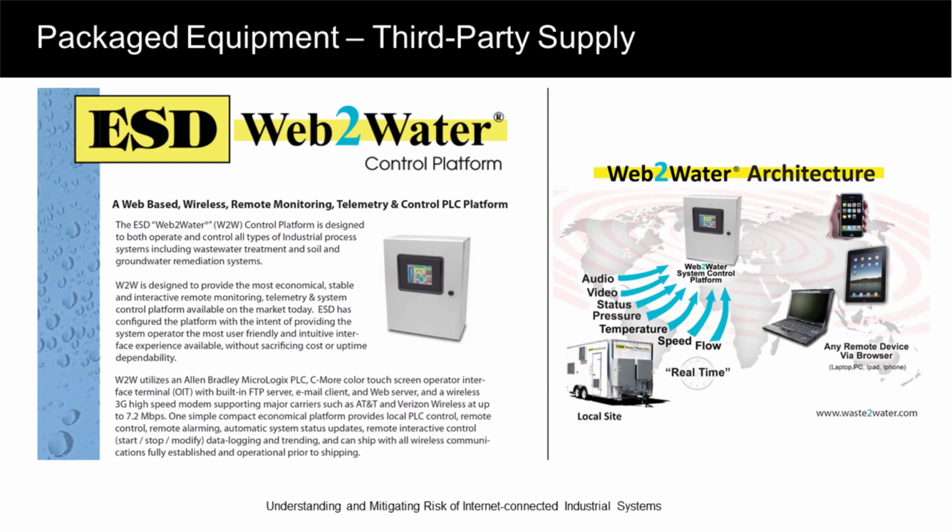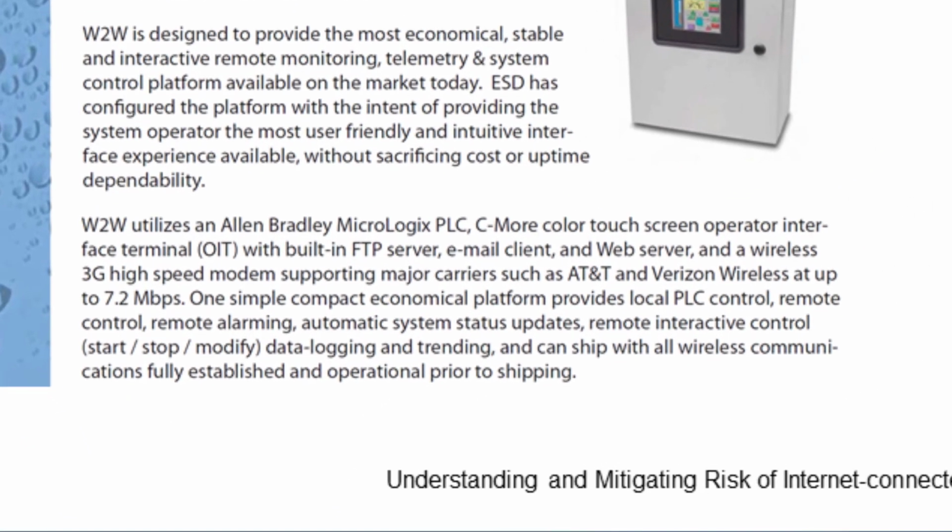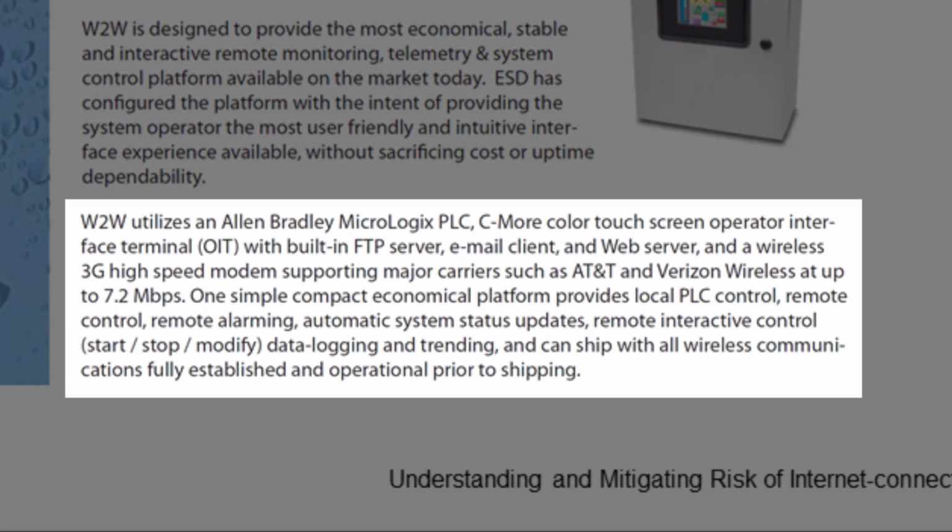So doing a little bit of research, just doing simple internet searches, I was able to disclose quite a bit of significant information about what was installed on this site before I ever visited it for the first time. If you look at this text provided by the supplier of this packaged equipment, they do a very good job of drawing an architectural picture for you that can help to understand not only its operation, but also its implicit risk. To begin with, they specifically name the manufacturer of the programmable logic controller.